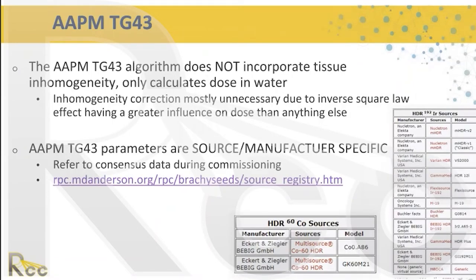The TG-43 algorithm does not incorporate any tissue inhomogeneity — it only calculates dose in water. The general clinical perception is that inhomogeneity correction is mostly unnecessary due to the inverse square law having much greater influence on dose. With advances in automated treatment planning and inverse optimization, it is now easier to include heterogeneity corrections if centers choose to, but we want commissioning to be at least consistent with the TG-43 formulas.